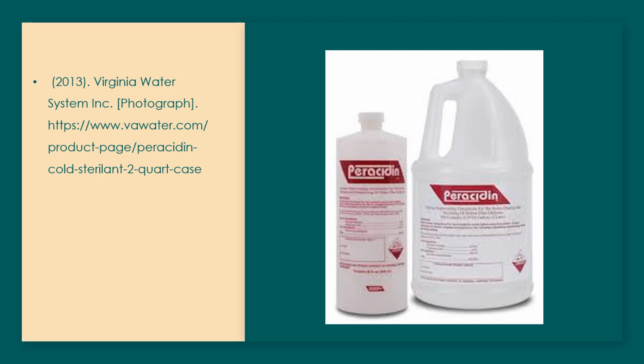Peracetic acid is one of the solutions you can use in cold chemical sterilization. This solution is most commonly used in the OR, and some of the instruments that are commonly used with this are cords, cameras, and scopes.